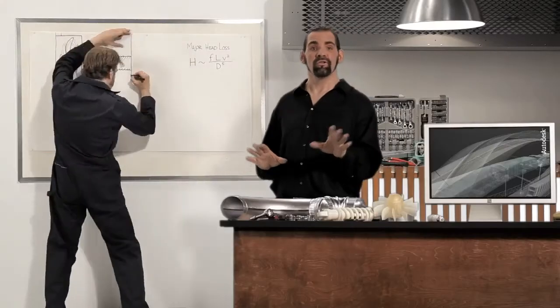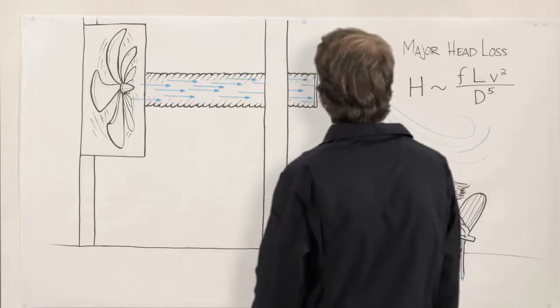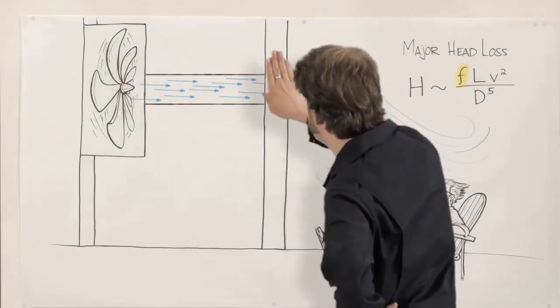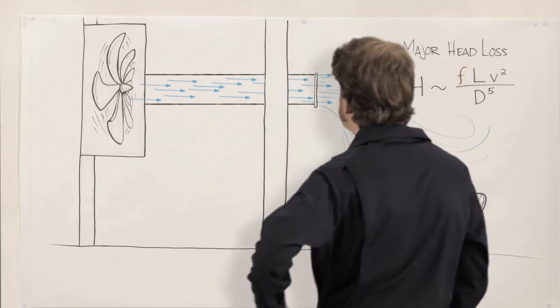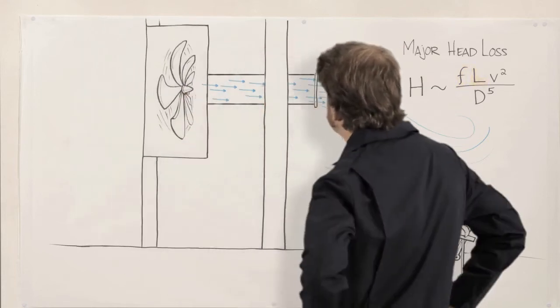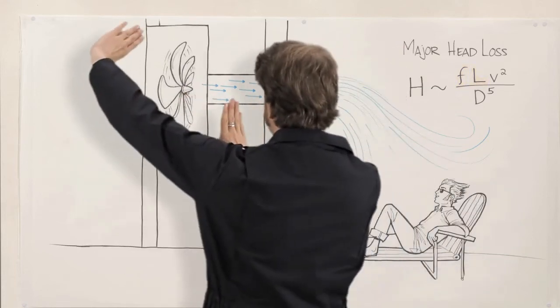Let's say you're pushing air through the ducts in a building. To reduce major head loss, you can make the duct smoother to reduce surface friction. You can reduce the length. And for a big improvement, you can reduce the velocity.